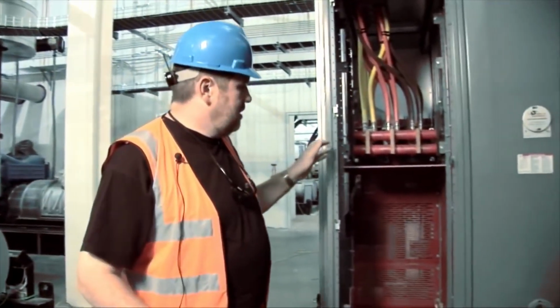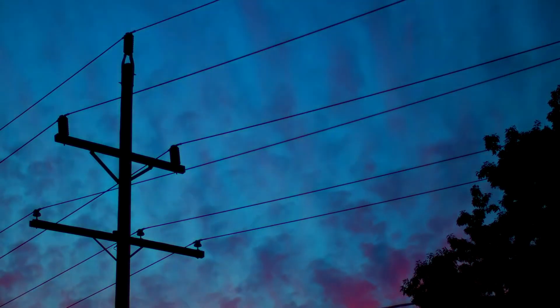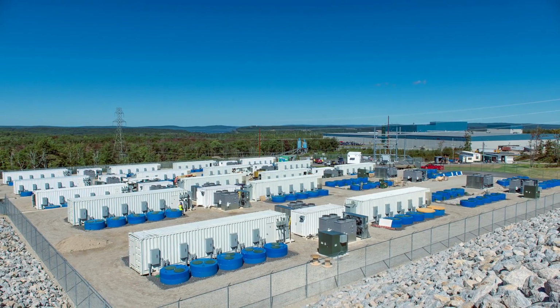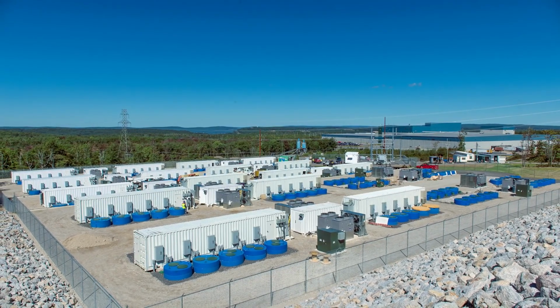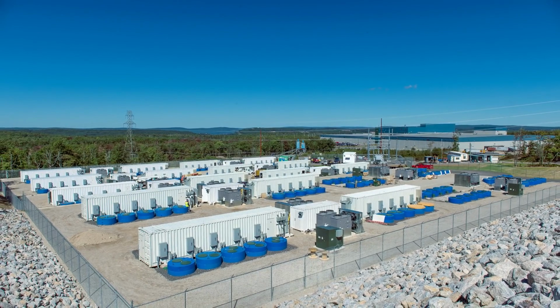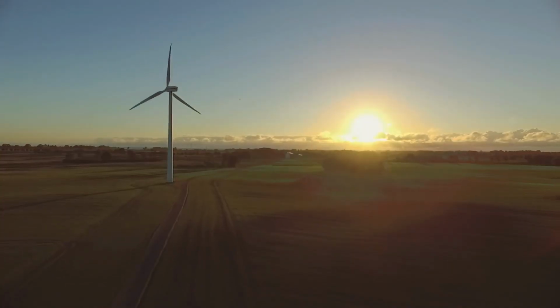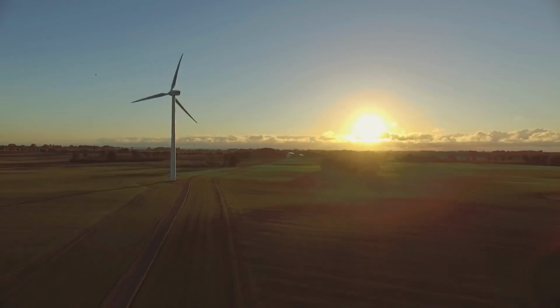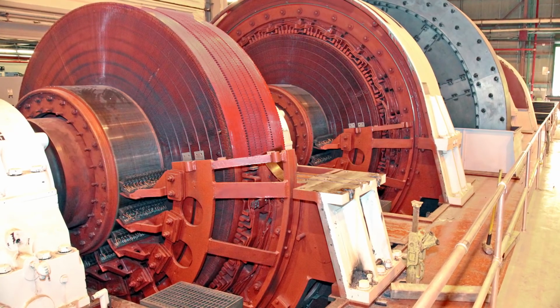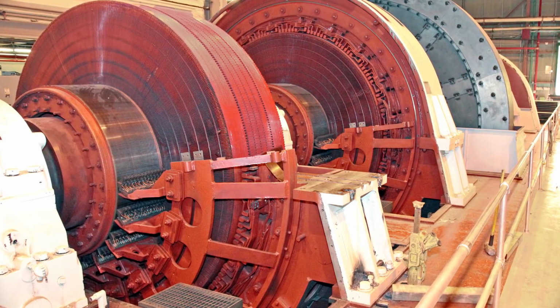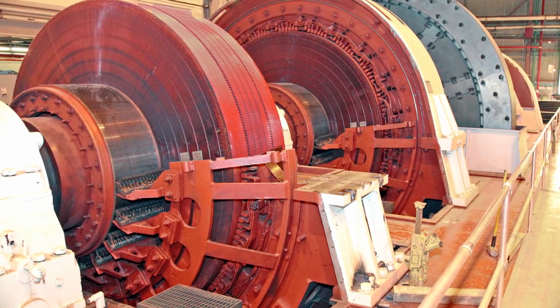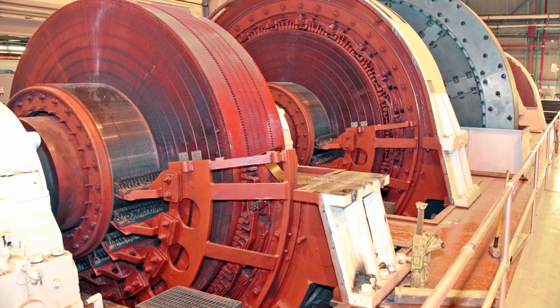their battery equivalent. Flywheel energy storage systems are also used in a similar manner at the power grid level, providing an energy storage buffer for balancing sudden changes between supply and power consumption. Several grid-level installations offering 2 to 20 megawatts of storage capacity with 15-minute discharge durations have been built throughout the United States and Canada. Demonstration projects based on storing wind power have also been constructed in California. At smaller scales, flywheel energy storage systems have been used where short bursts of power are needed without taxing power supply systems. Notable examples of this are installed at several physics laboratories worldwide, including many fusion experiments, in which megawatt bursts of power are needed to energize electromagnets for a few seconds.